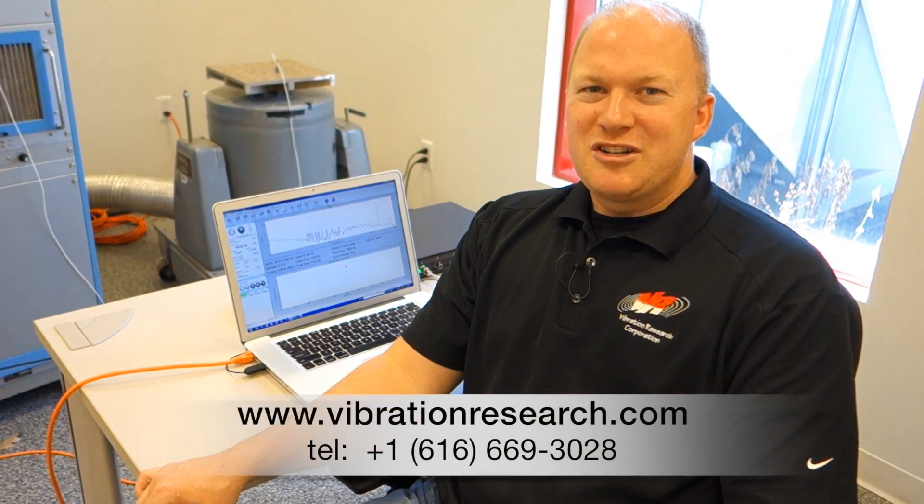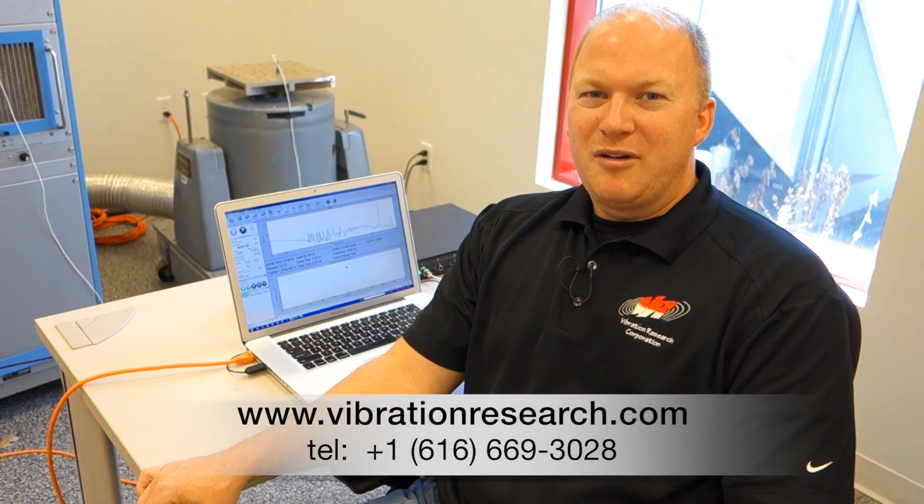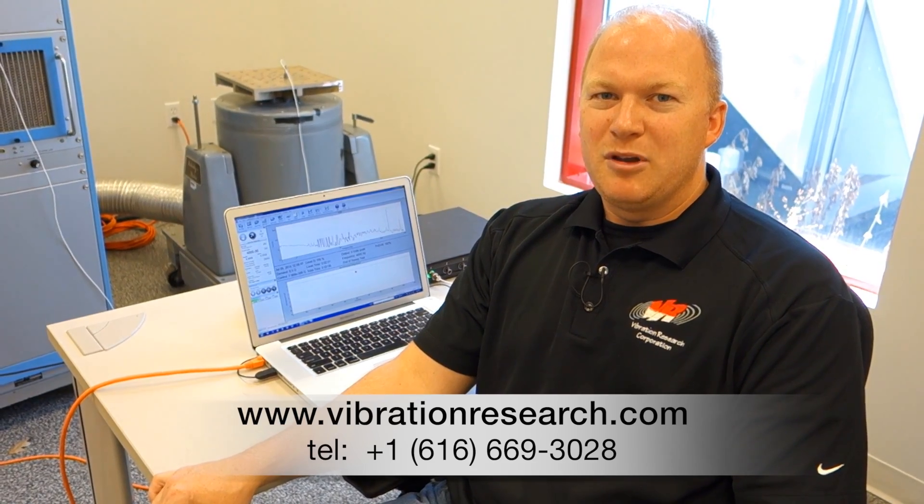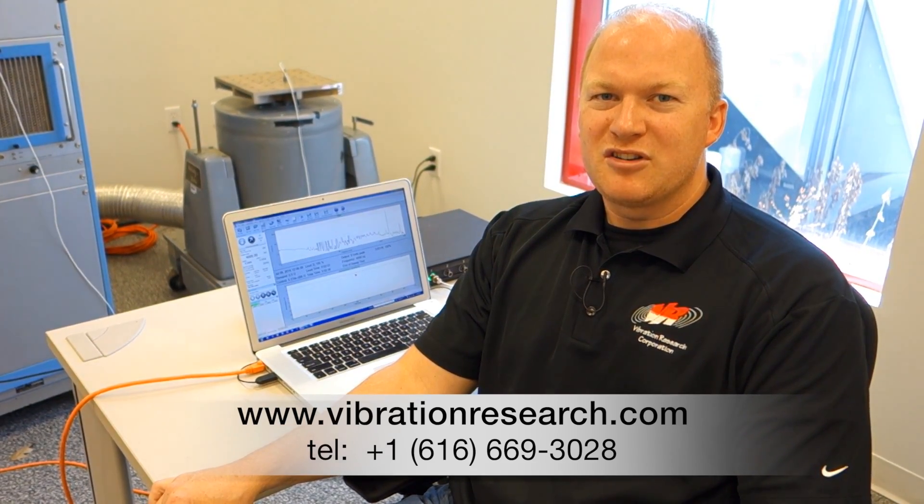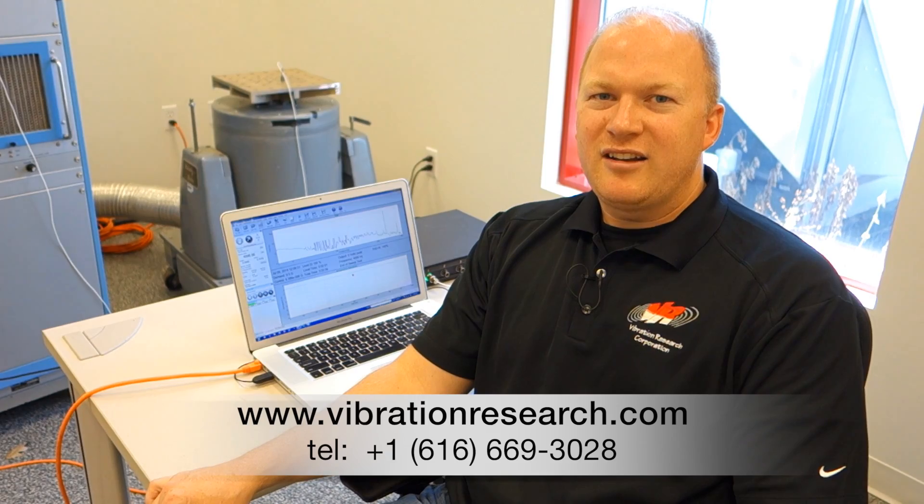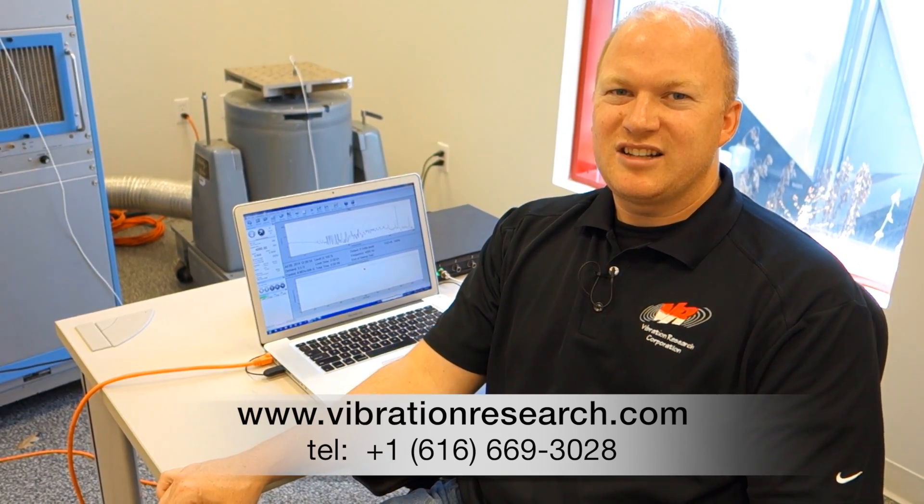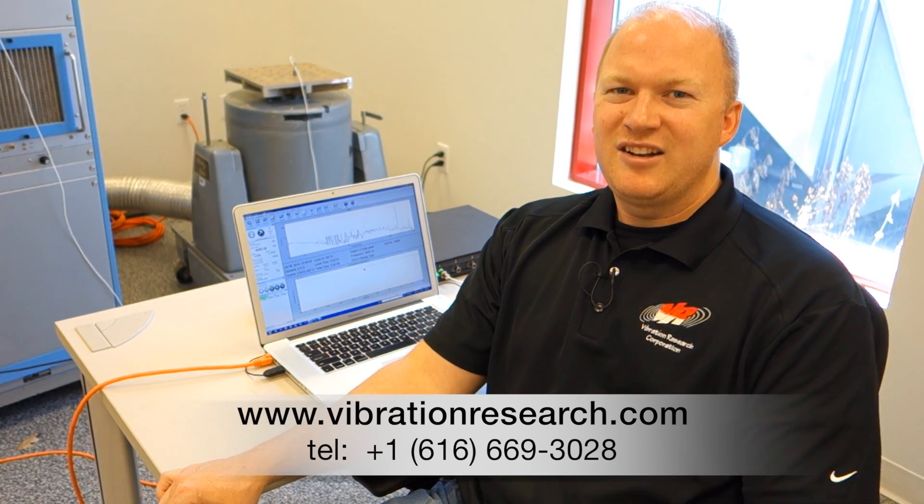This video demonstrates another tool from Vibration Research that you can use to determine the health of your system by measuring the THD. You can do this in a preventative maintenance program once a year even and track changes over time. You can also use this to compare different fixturing designs and product responses. You can get more information from Vibration Research on our website www.vibrationresearch.com or contact us directly at 616-669-3028.